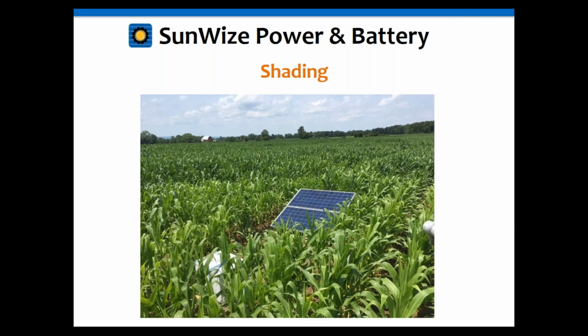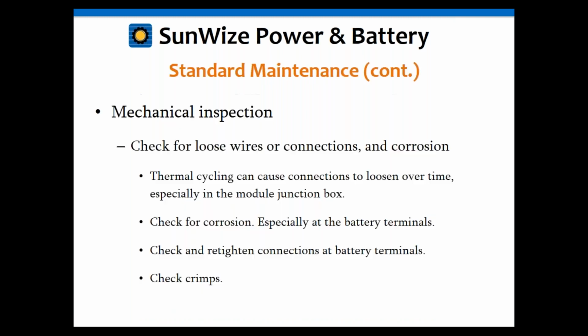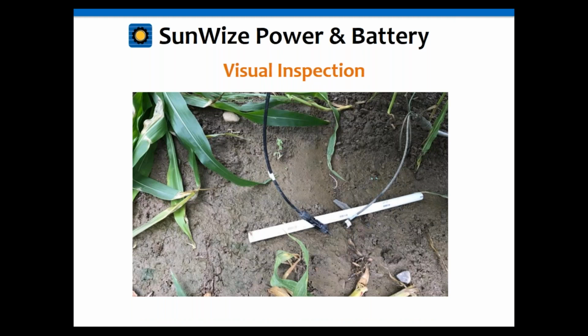Here's one where you can see in a cornfield where the corn has been planted and grown up around the solar modules, and therefore they do not work correctly because the corn is now shading it. And let's see, I'm going to skip to this one real fast. This is another one that was found where the wire actually got corroded. Here's an example of the wire, the insulation got chafed, and then the copper wire was exposed.